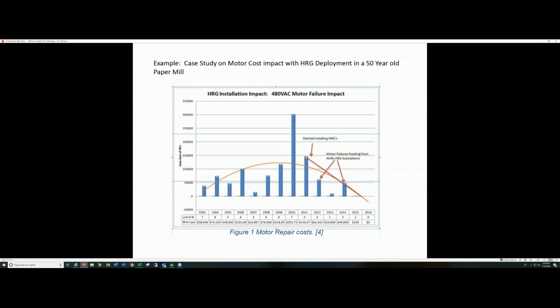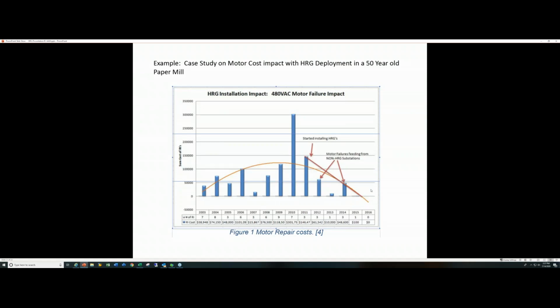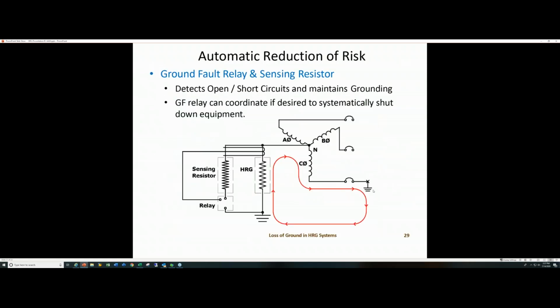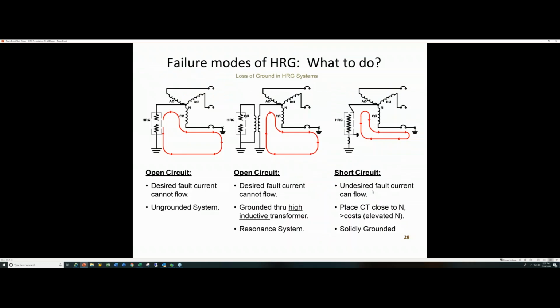And we started deploying HRGs the first year, the second year, the third year, and the fourth year. And these motor failures that caused these higher levels than normal were actually due to substations that weren't HRG protected at the time as we were deploying these HRGs. So they caused a little bit of impact. But right now we're still on this trend of very minimal motor costs due to faults.